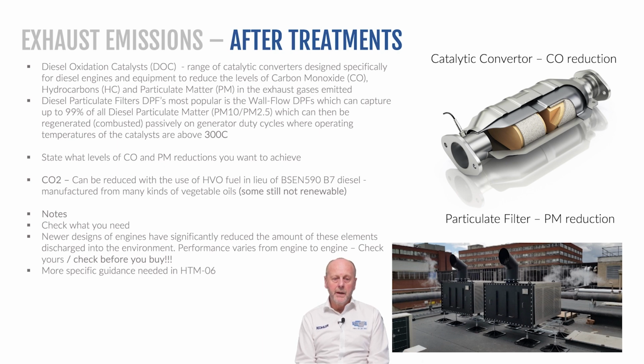So before you apply any of these after treatments, you need to check what your engine is actually delivering into the environment. To be clear, all engines sold in the UK will meet UK emissions requirements. Newer designs will achieve much higher levels than some of the older designs. So all of this you need to be validating through the tender process when you're procuring a new generating set. All of these devices that I mentioned can be fitted, but there needs to be clarity on what the objectives are that you're trying to achieve. So to what degree do you want to reduce CO? To what degree do you want to reduce PM10?